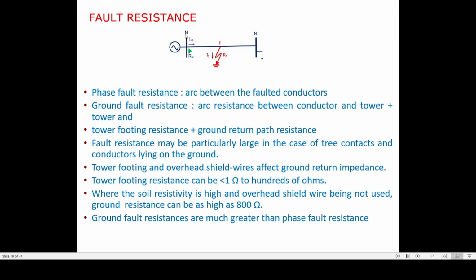happen is that for the power to flow from substation M to substation N, the voltage angle at M must lead the voltage angle at bus N. That means the current at bus M is leading the current at bus N, and this angle difference of current, or angle difference in the current prior to fault, has more and more effects on the performance of distance protection, and this effect keeps on increasing with the inclusion of fault resistance.